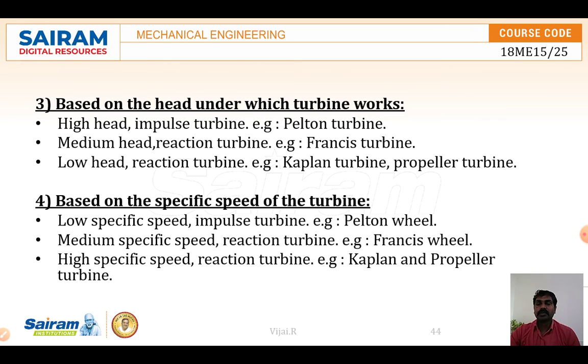So this is based on the head. Head means pressure head. How much pressure the water can create, and how much pressure it can hit on the turbine. It is based upon the head under which the turbine can work. The Pelton wheel turbine can withstand a high head, so we call it a high head turbine. And medium head is a reaction turbine.